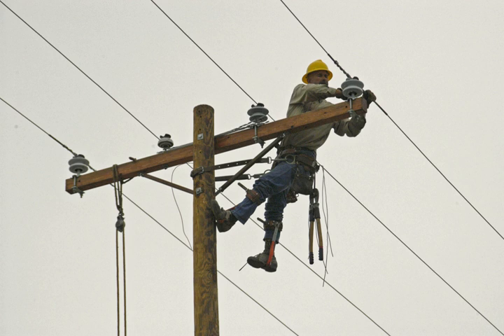Isolated line work is only used for transmission level voltages and sometimes for the higher distribution voltages. Live wire work is common on low voltage distribution systems within the UK and Australia, as all linesmen are trained to work live. Live wire work on high-voltage distribution systems within the UK and Australia is carried out by specialist teams. Work on outdoor tower construction or wire installation is not performed exclusively by linemen. A crew of linemen will include several helpers. Helpers assist with on-the-ground tasks needed to support the linemen, but may not work above ground or on electrical circuits.